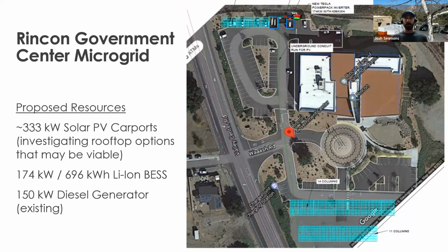There wasn't an ongoing operations and maintenance plan, and issues started happening and people lost sight of it. There wasn't data available on how well they were performing or not. So right now we're in the process of getting the tracker systems replaced. There were some damaged panels. There are all these things now that we're trying to unwind, and there were lost months to years of production in some of the arrays because there wasn't ongoing operations and maintenance.